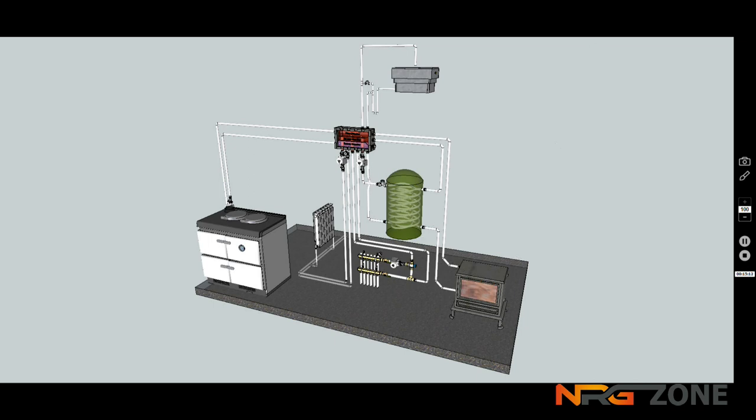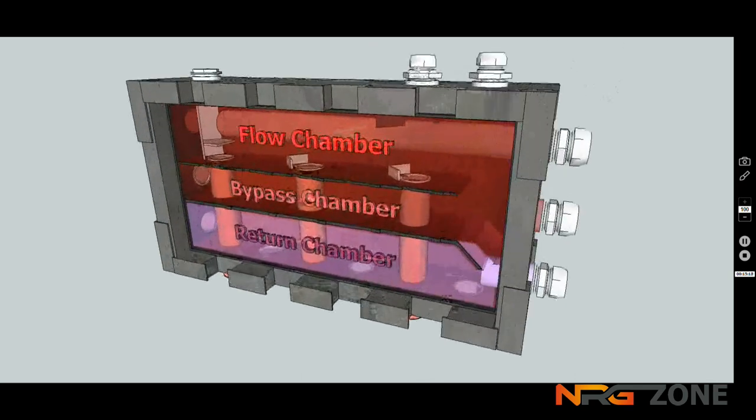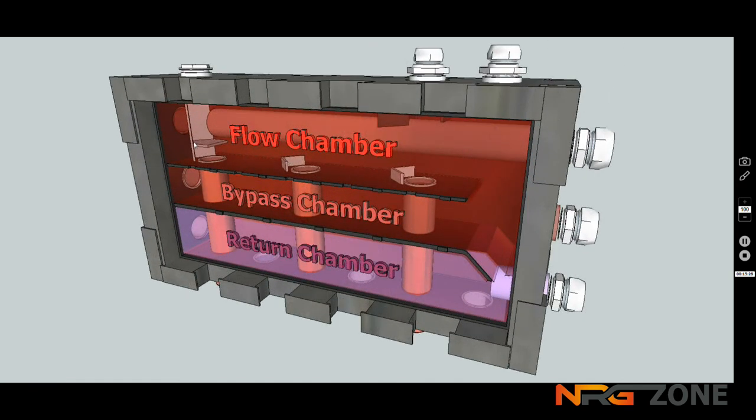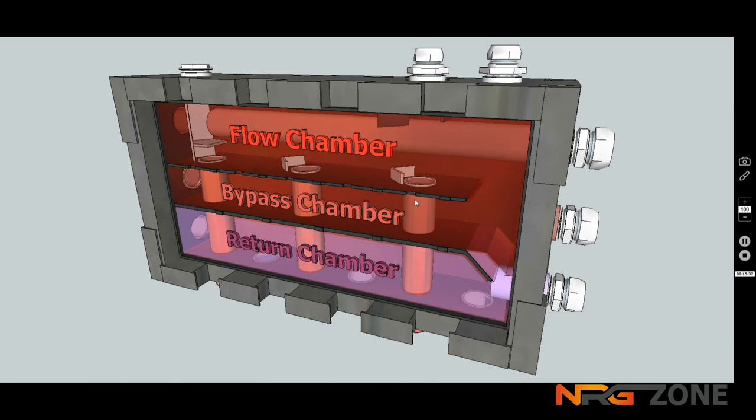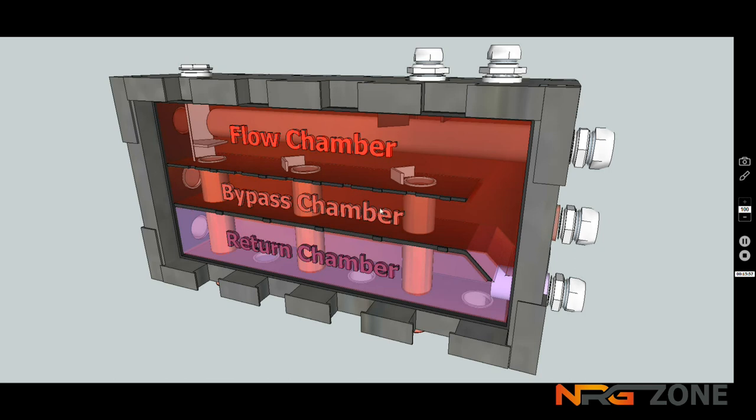Now, again, if you look at the energy zone, you'll see that the energy zone has given us this cold chamber, which is the optimum way of dealing with delivering water back to the coldest appliance. And also, you'll see where the water flows through. Any water traveling in that system will always, if it comes from here or here, will always travel along. Because this area in here is so many times bigger than the pipe delivering, the air will start to collect here, and it'll be trapped in this configuration, and directed out and up out of the expansion. So every time water passes through the system, the unit de-aerates that water, so there's no air in the system. It solves the problem of airlocks in radiators or whatever. It's continually venting the system.